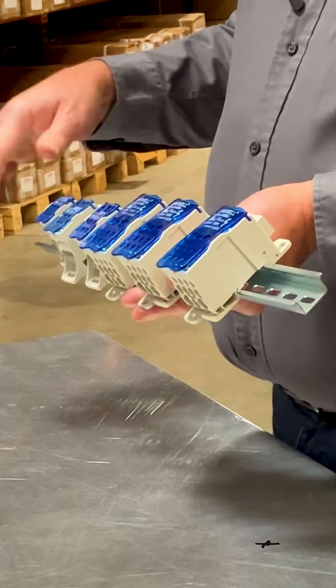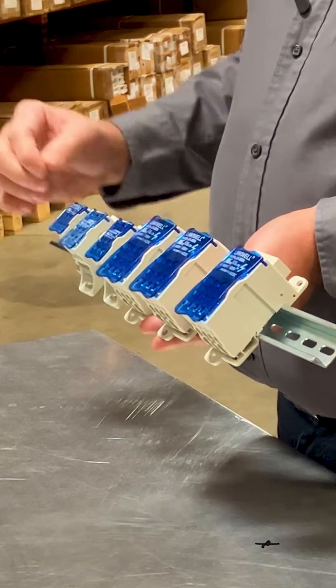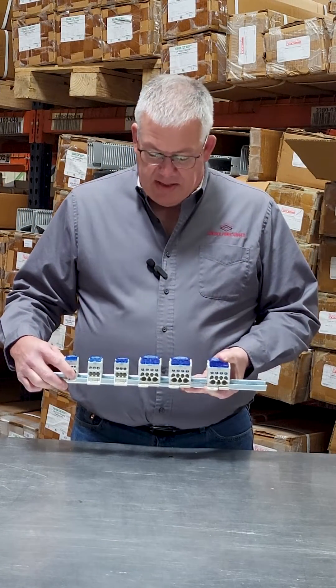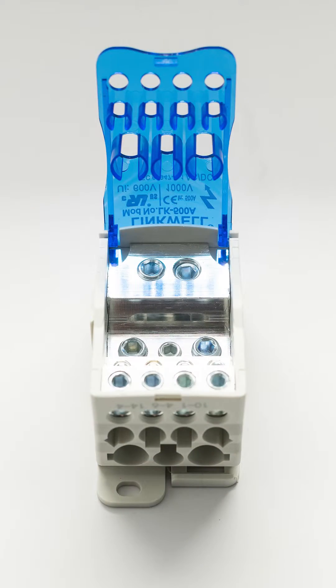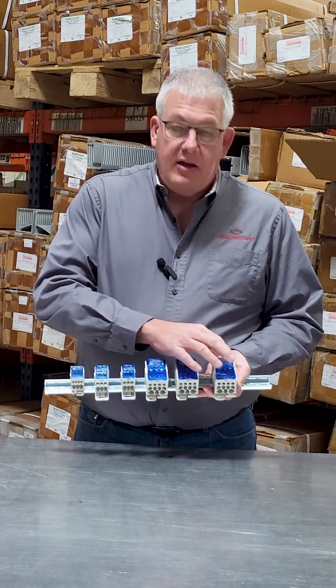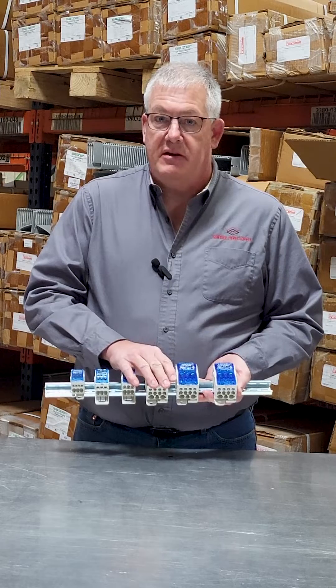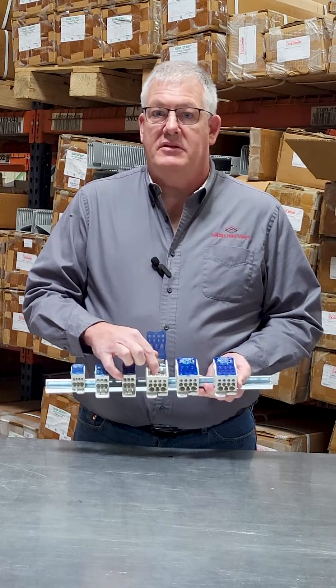They mount on either standard 35 millimeter DIN rail or they can be panel mounted directly with screws. Each one is marked with laser markings on both the line and the load side which lists your wire sizes that are available. The material is constructed with flame resistant nylon PA66 material and the conducting material is tinned copper construction.